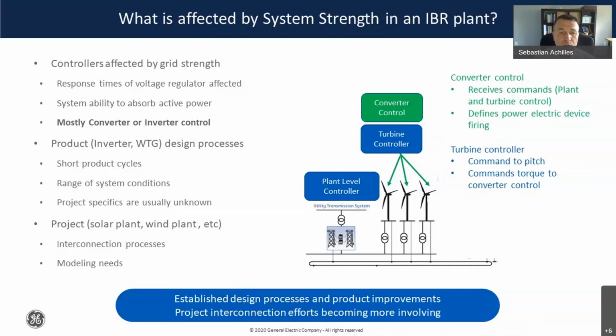For the plant level controller, it's different, particularly for voltage. On one side it's different because you have one plant level controller per plant, not 100 like you have turbines. But on the other hand, the voltage regulation aspects are more project-specific, because the impedance seen by the controller is even more affected by the system strength in the utility than the converter control is.